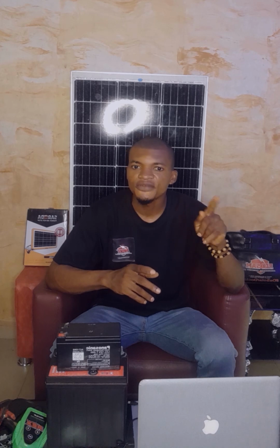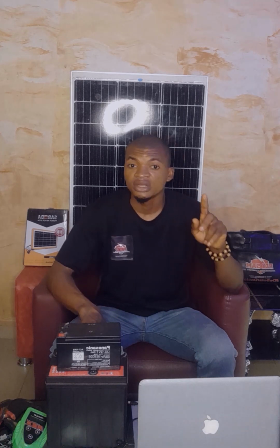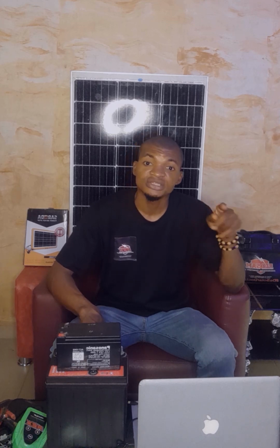So let's say we are going to run a load of 1000 VA with a battery of 12 volts by 200 amps. I'm going to calculate it, just follow my steps. First, time equals battery voltage multiplied by battery amperage, all over the load. Inputting the figures: my battery voltage is 12 volts times my 200 amp-hours, all over my 1000 VA. Calculating this, I get 2400 divided by 1000.